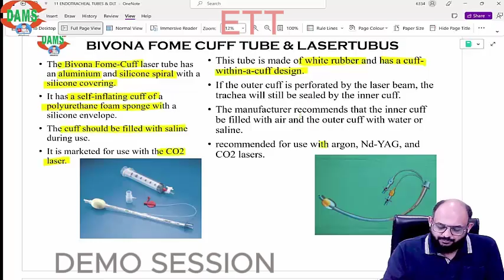Now Bivona foam cuff tube and Laser Tubus. Bivona foam cuff has an aluminium and silicone spiral with a silicone covering. Okay. It has a self-inflating cuff made up of polyurethane foam sponge. I told you, the foam cuff. Okay. Cuff should be filled with saline and it is marketed for CO2 laser. While Laser Tubus is a tube made up of white rubber and has a cuff within a cuff system. So it is also dual cuff but cuff within a cuff. So in case the outer cuff gets damaged, the inner cuff will take over, and it is for argon, Nd:YAG and CO2 laser.